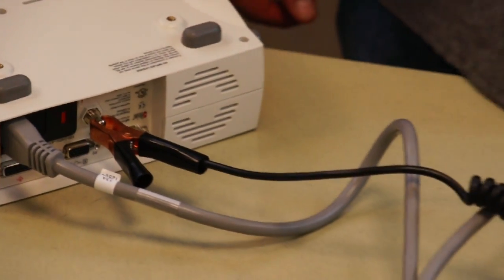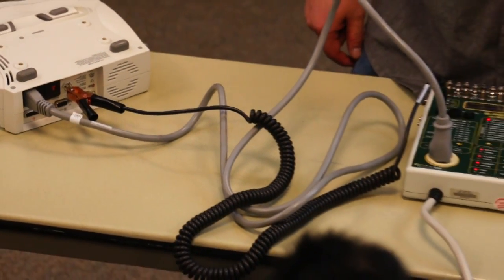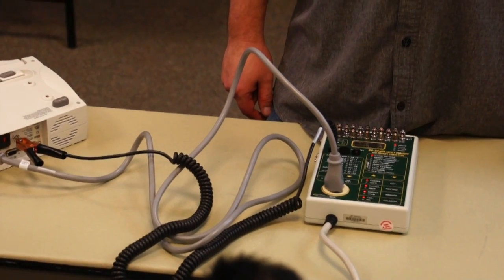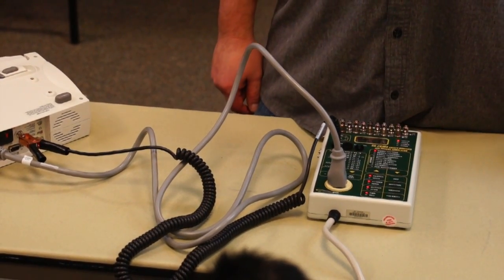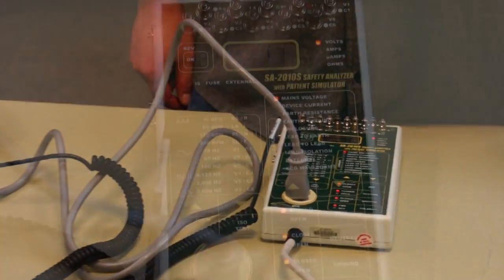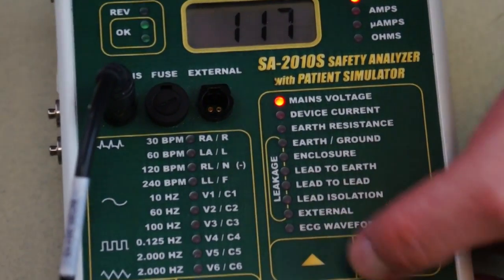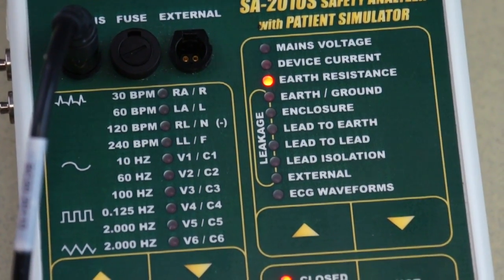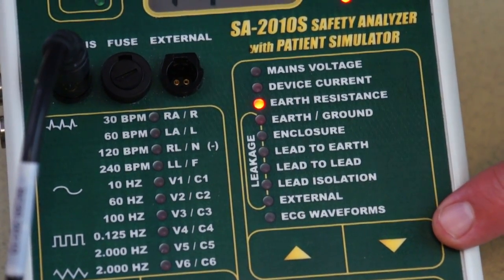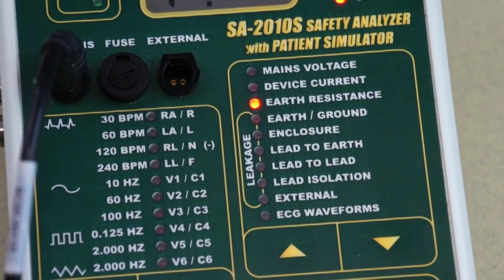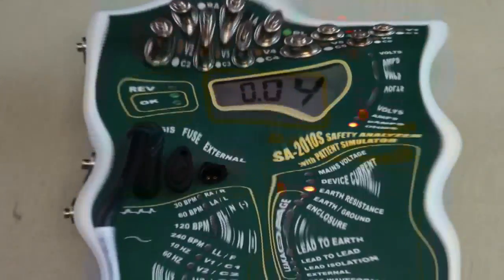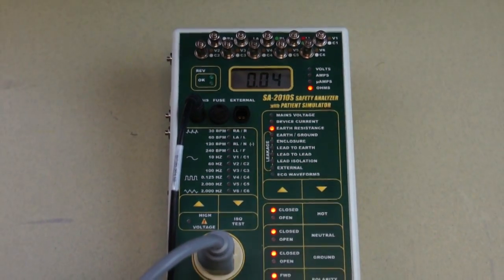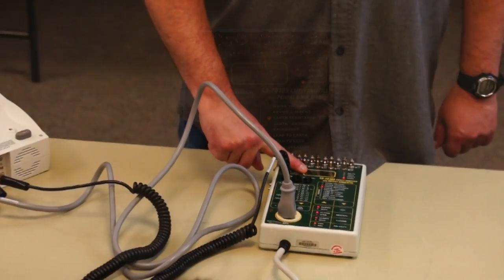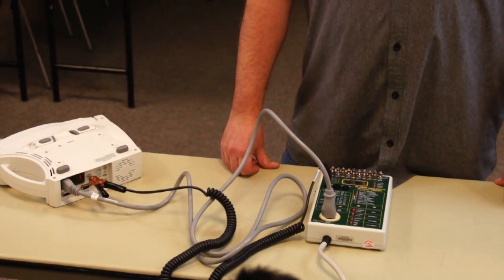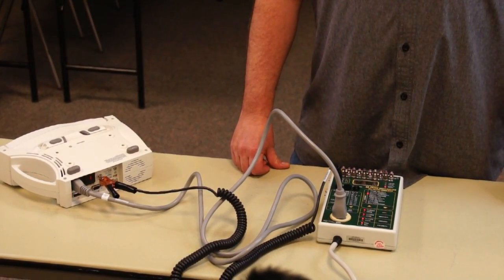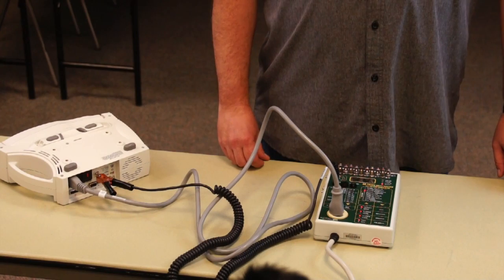Now that our setup is correct, we will set the mode of our safety analyzer to earth resistance. This is done by pushing the down arrow 2 times. The LED will now indicate earth resistance and the units will be listed in ohms. Our device under test is currently showing 0.04 ohms. In order for this device to pass, the value needs to be 0.5 ohms or less. Therefore, this test is a pass.